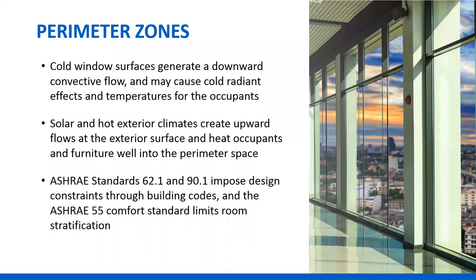There are regulations. ASHRAE 62.1, the ventilation standard, talks about avoiding ventilation short circuiting that results from putting hot air out at the ceiling, which causes the room to stratify. ASHRAE 90.1 says you can't heat air that's been previously cooled. Standard 55, the thermal comfort standard, limits the occupied zone — floor to six feet — to 5.4 degrees Fahrenheit vertical temperature stratification for comfort. All three of these constrain what we want to do in a perimeter zone.